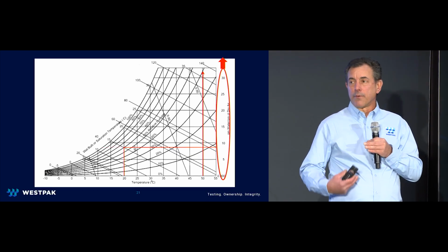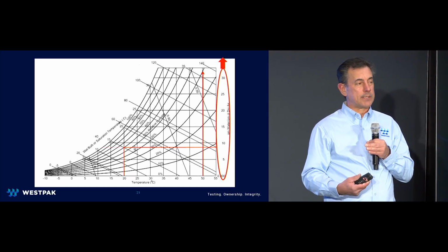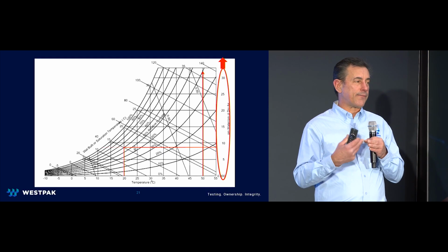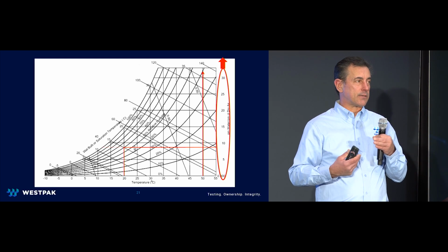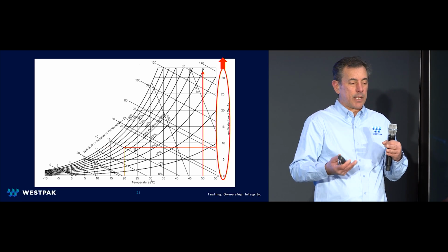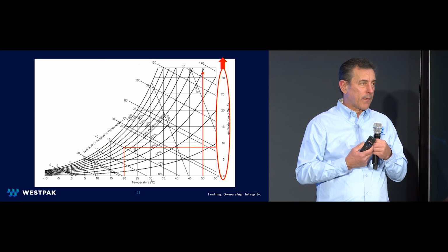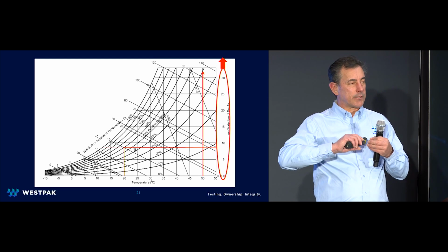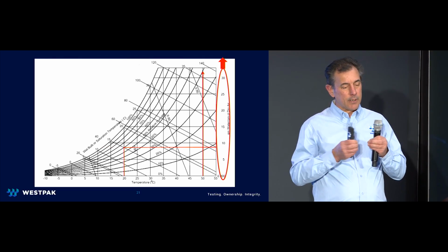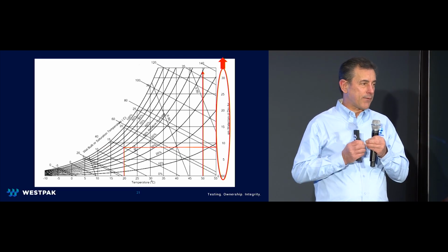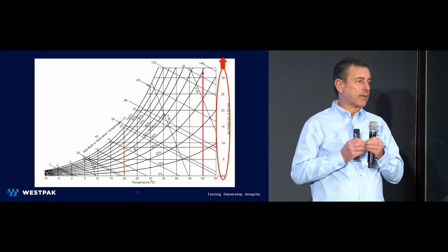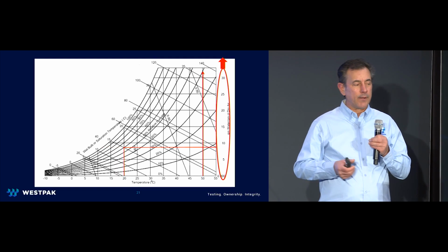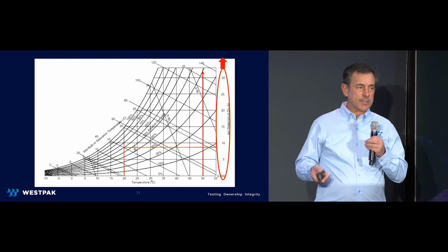So once we get the test results back, it's going to be up to you to evaluate your device to make sure that it's going to stay in a stable condition. Stable condition, again, acceptance criteria. Could that be tension? Could that be torsion? Could that be adhesives that moisture has a negative effect or impact on? Those are the things that we need to identify, and also the materials themselves.